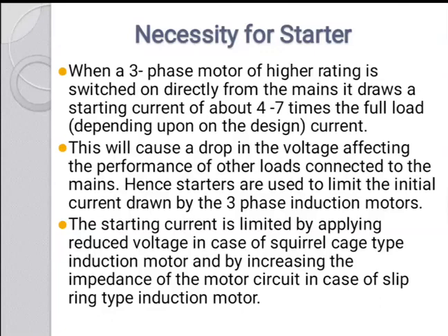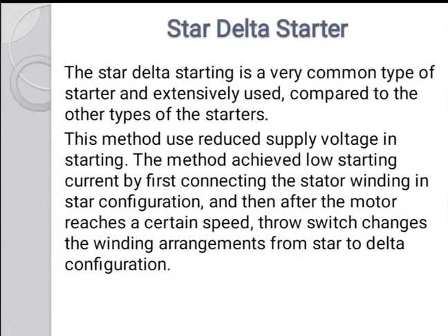That will affect the loads connected in that particular area. Therefore, starters are very much necessary for three-phase induction motors to limit the starting current. The starting current is limited by applying a reduced voltage in the case of a squirrel cage induction motor, and by increasing the impedance of the motor circuit in the case of a slip ring induction motor.